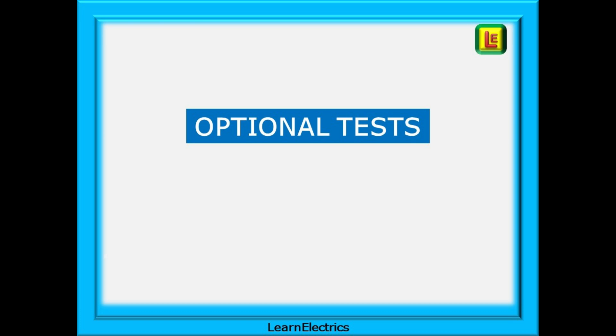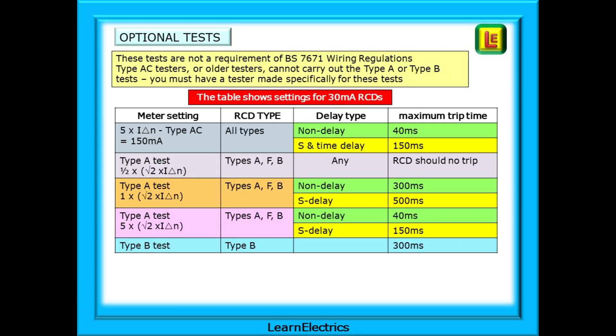There are optional tests that can be carried out, but they are not a requirement of the wiring regulations. This table shows the optional tests available. These are not required by BS 7671, but results should be noted in the remarks column of the schedule or on the back of the certificate. Type AC testers or older testers cannot carry out type A or type B tests — you must have a tester made specifically for these optional tests.